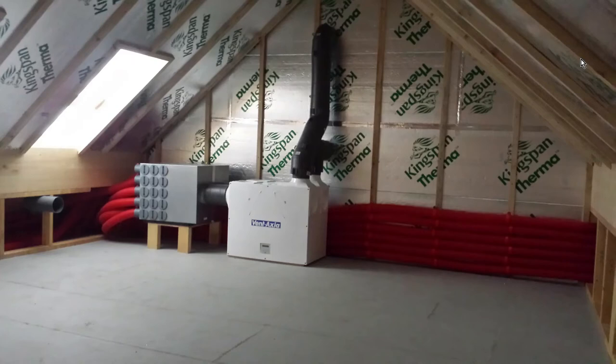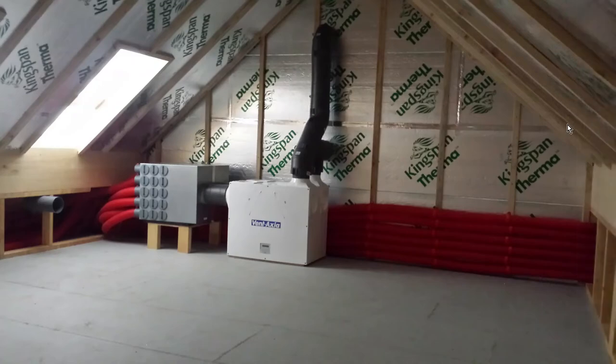Here's a great install. Decent machine sitting on an anti-vibration mat. Super insulated expanded polypropylene ducting so there's no condensation problems. Comes in at high level goes out to low level so you don't suck the stale air back in. It's got two acoustic manifolds connected to the best radial ducting on the market all hidden in the eave space nice and tidy easy to box in very compact. Everything is inside the thermal envelope which keeps all the heat inside the property.